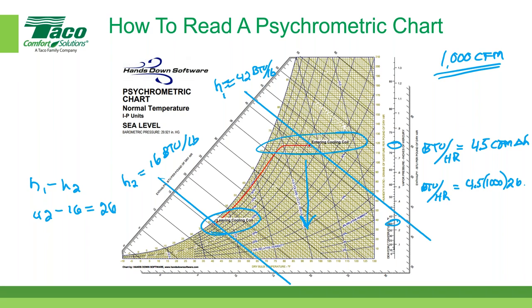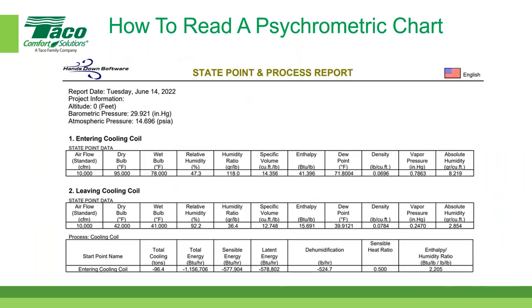And if I did my calculation, let's see how accurate I am, Brett. I have a calculator in front of me. So it's 1,000 times 4.5 times 26, and that means 117,000 BTUs per hour. If I take that and divide it by 12,000, I can turn that into tons. Divided by 12,000, that's equal to 9.75 tons of cooling. Isn't that cool? All that from those two numbers. I think I actually plotted that out. There it is right there.